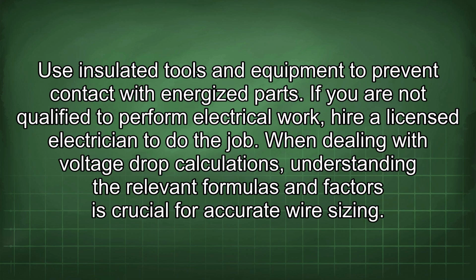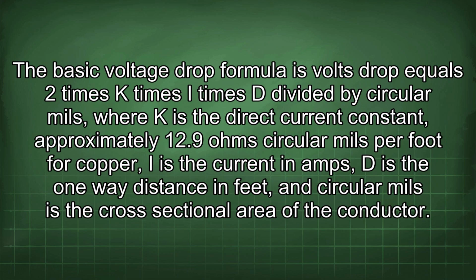When dealing with voltage drop calculations, understanding the relevant formulas and factors is crucial for accurate wire sizing. The basic voltage drop formula is volts drop equals 2 times K times I times D divided by circular mils, where K is the direct current constant, approximately 12.9 ohm-circular mils per foot for copper, I is the current in amps, D is the one-way distance in feet, and circular mils is the cross-sectional area of the conductor.